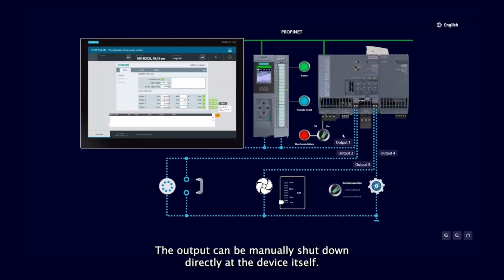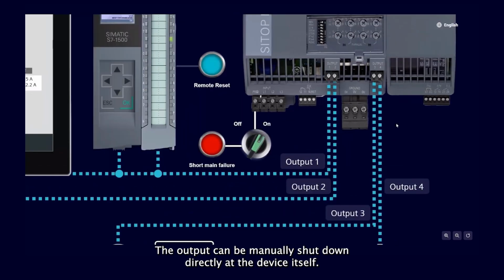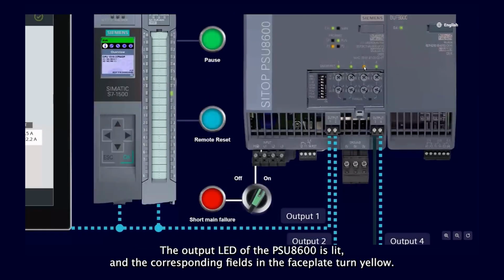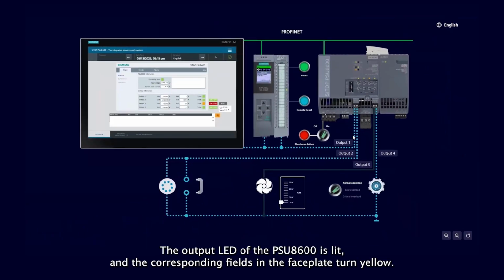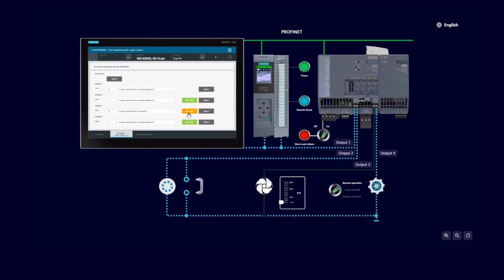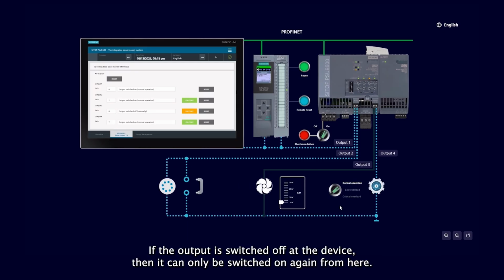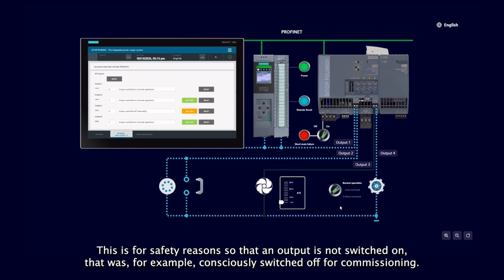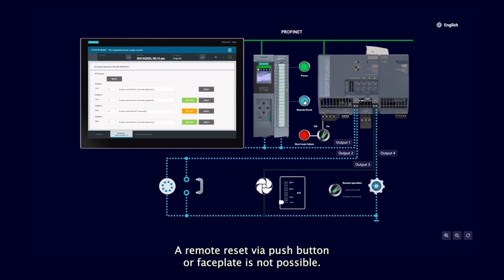The output can be manually shut down directly at the device itself. The output LED of the PSU8600 is lit, and the corresponding fields in the faceplate turn yellow. If the output is switched off at the device, then it can only be switched on again from here. This is for safety reasons, so that an output is not switched on that was, for example, consciously switched off for commissioning. A remote reset via push button or faceplate is not possible.